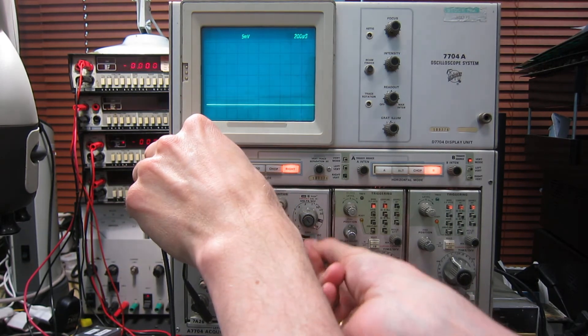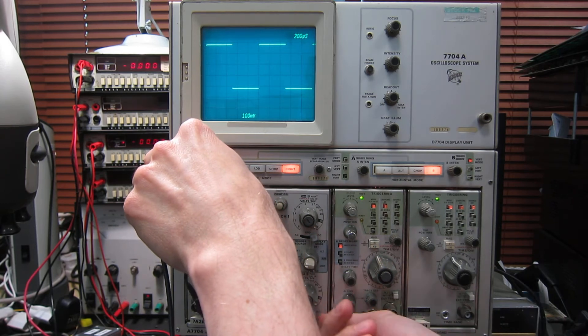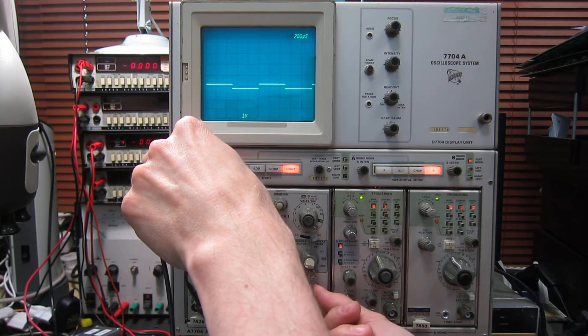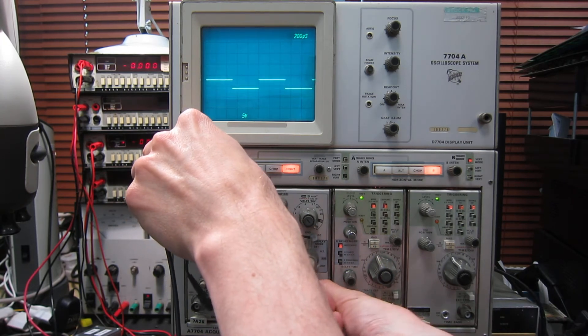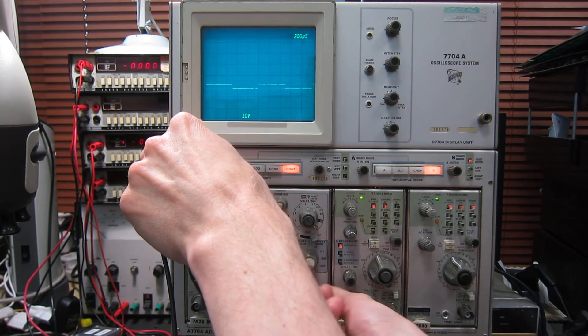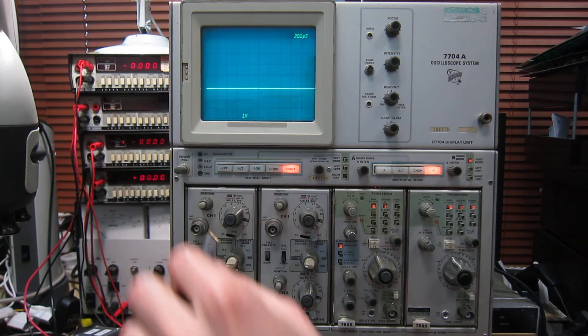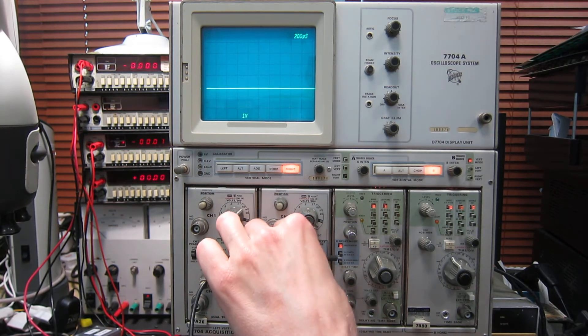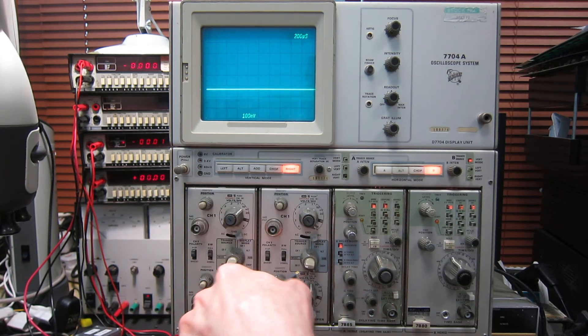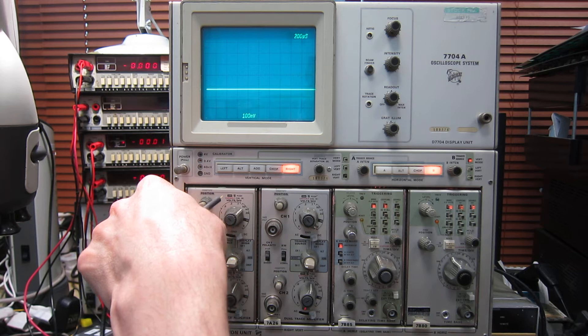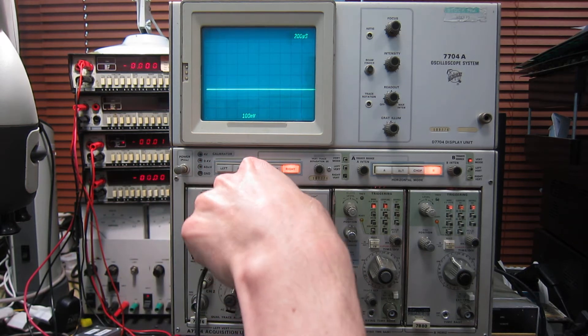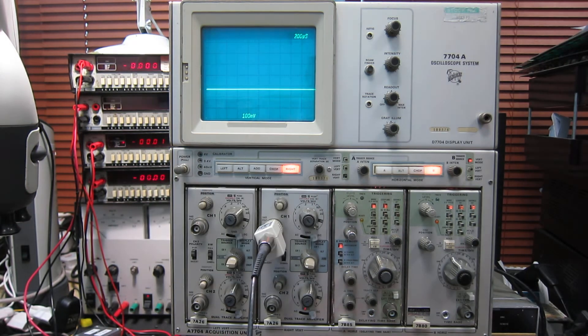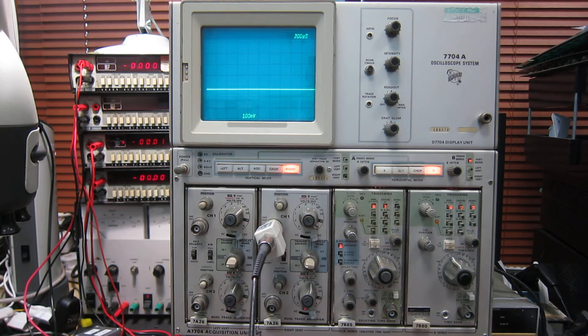There we go. We've got that going nicely. So yeah, that's all the attenuator settings working. They have a switchable bandwidth, these plug-ins as well, which is quite nice for cleaning up the trace. If you don't need the full 200 MHz bandwidth, you can limit it to 20 MHz.